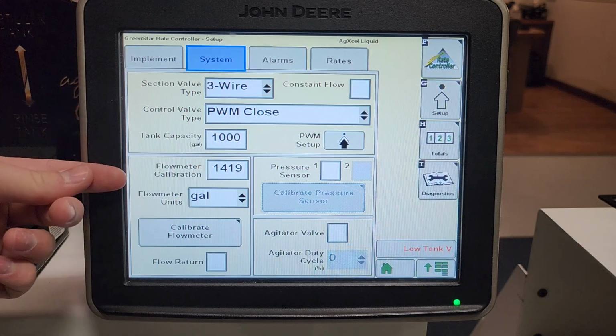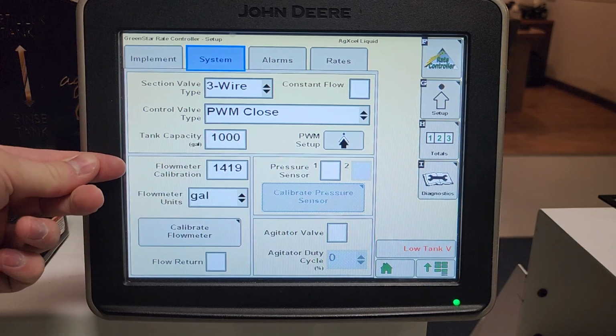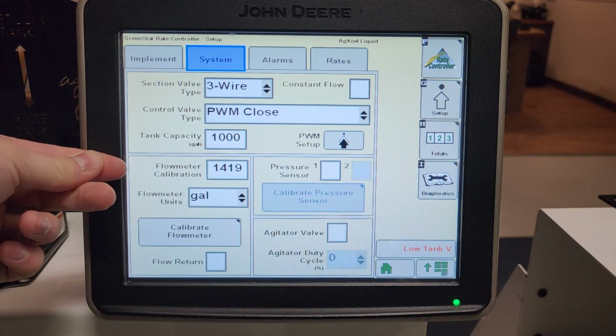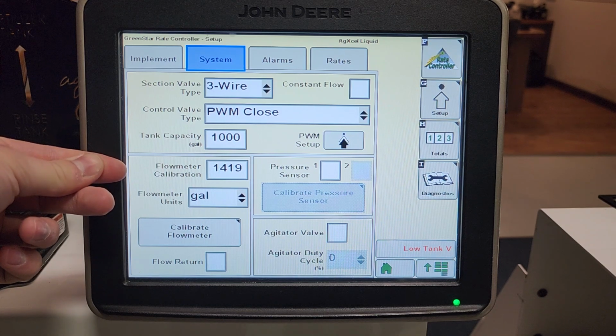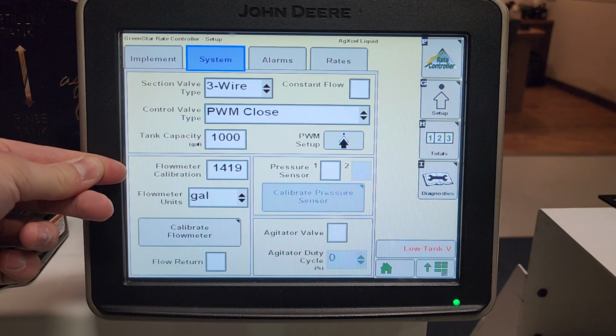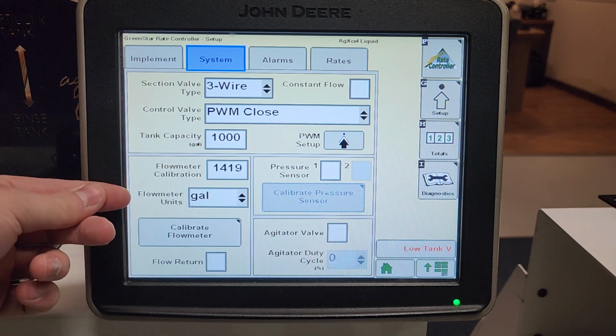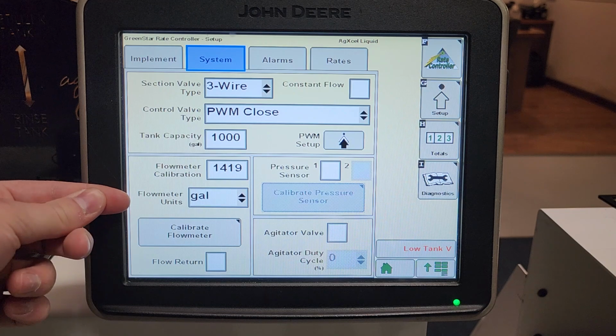Normally you can put that into your rate controller, but in the case for the Green Star, you have to divide that number by 8, and then this would be the flow meter calibration that you come up with. In this case, since the flow meter I'm using is 0.3 to 5 gallon per minute, my pulses per gallon is 11355, but I have to divide that by 8, which comes up to 1419. So that will be my flow meter calibration. And then your flow meter units will always be in gallon, just GAL.